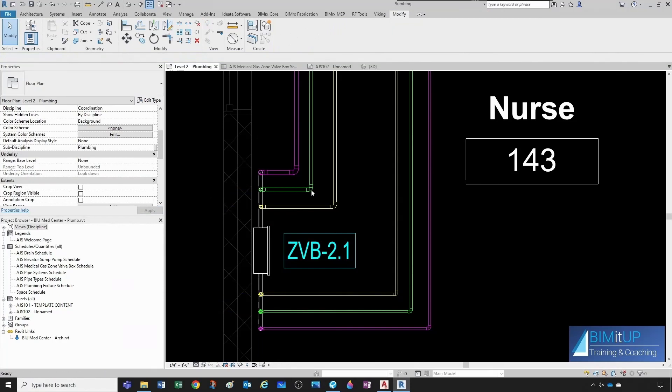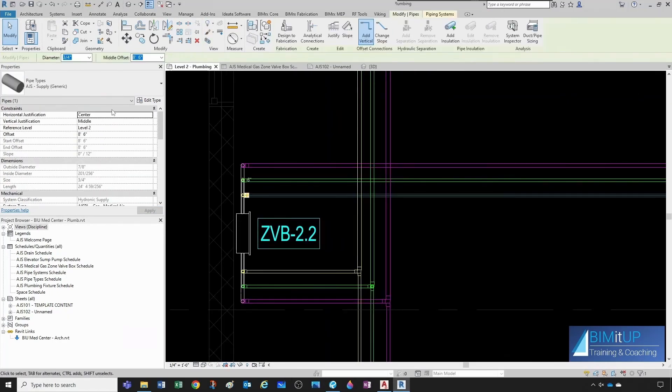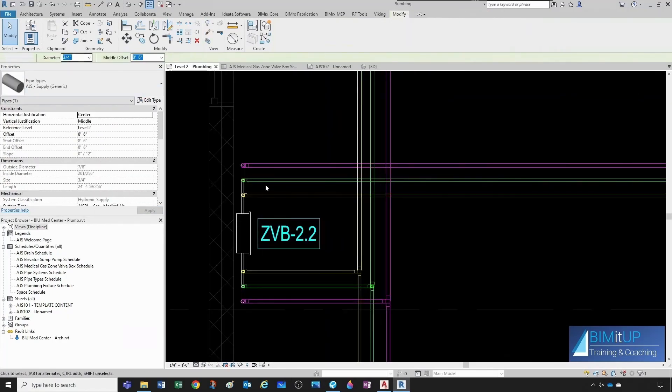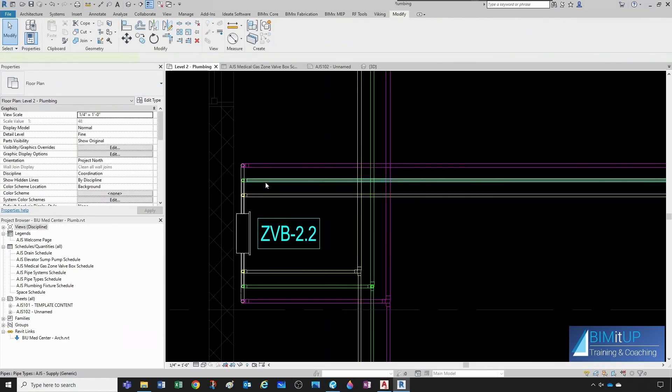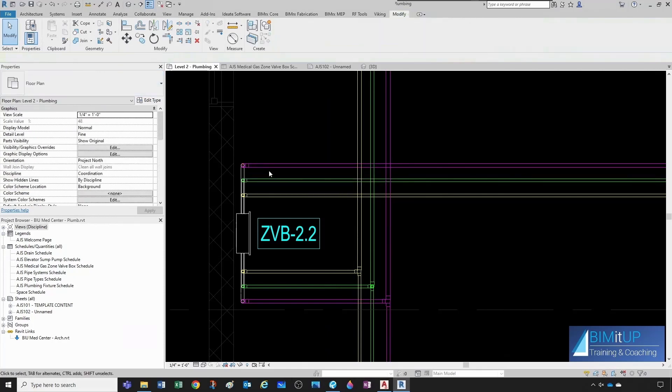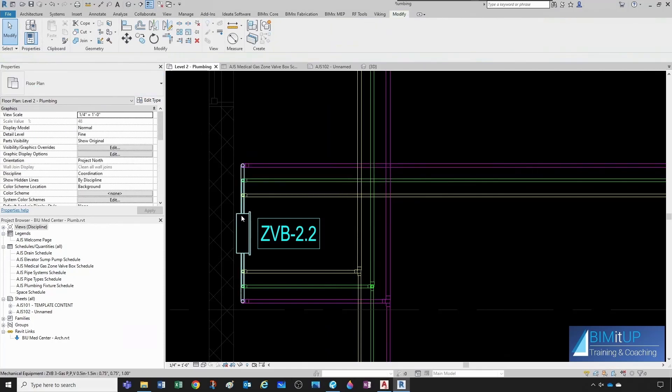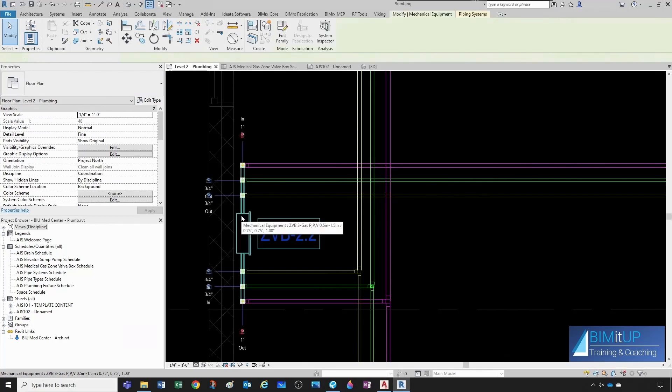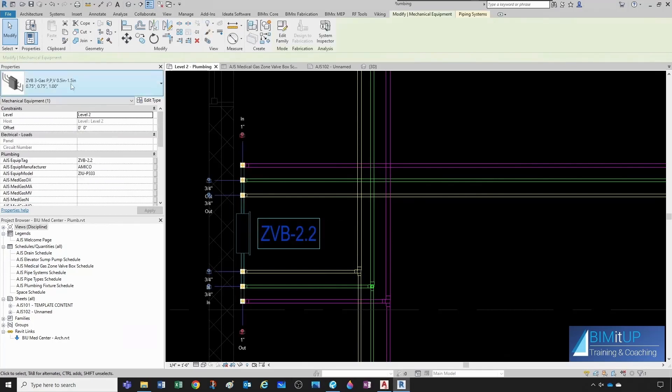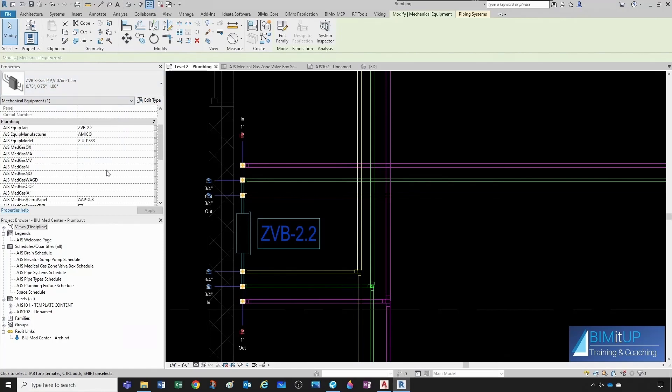All right, and then this one here has three quarter inch medical air, three quarter inch oxygen, and one inch medical vacuum. So, three quarter inch, three quarter inch, one inch, and that's good.